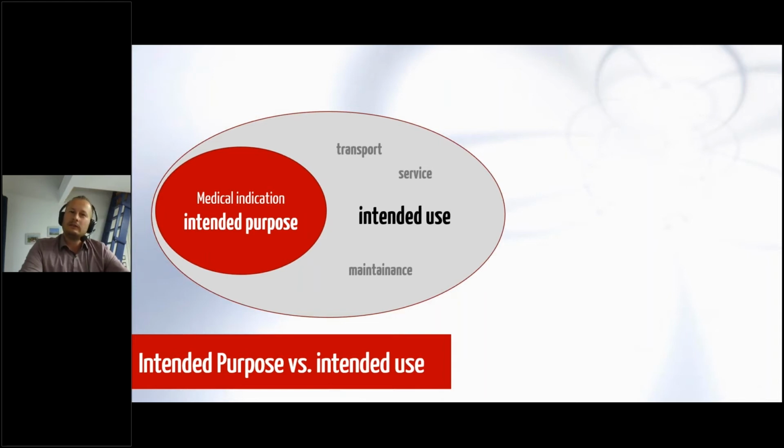So the intended purpose is defined by the medical indication, whereas the intended use includes as well transport, service, and maintenance, in addition to the medical indication to the intended purpose.